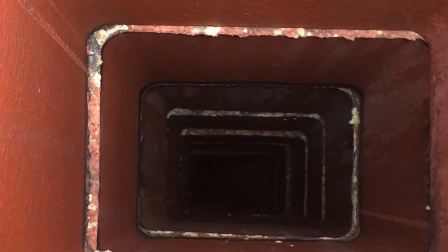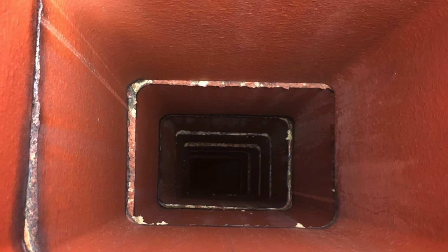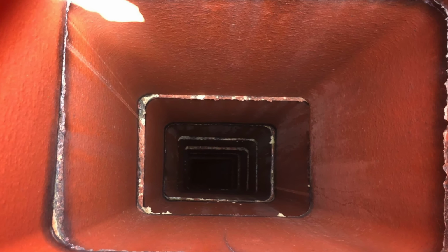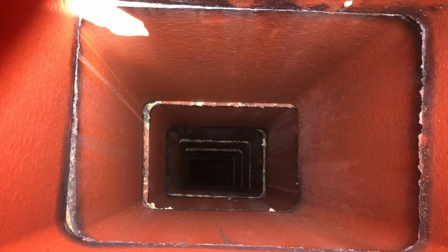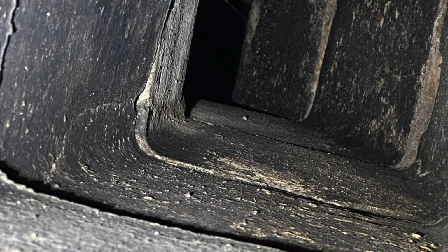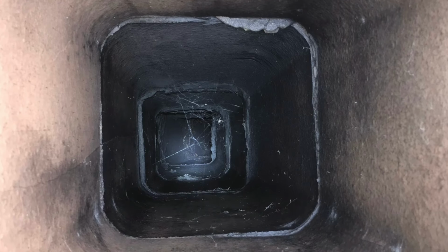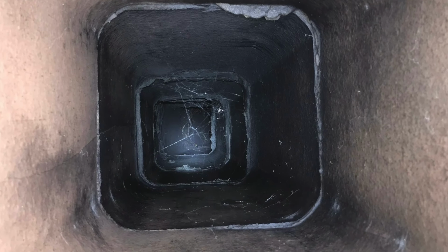Proper chimney liner construction is essential for both safety and performance, and several standards guide how flue liners must be installed within a masonry chimney. The best chimney liner systems run vertically in a straight line because straight vertical flues draft more efficiently and reduce turbulence and soot accumulation. When a change in direction is unavoidable, the bend must be made with a clean saw-cut liner section, and the angle of deviation from vertical may not exceed 30 degrees. This ensures that the flow of exhaust gases remains smooth and that creosote formation is minimized.